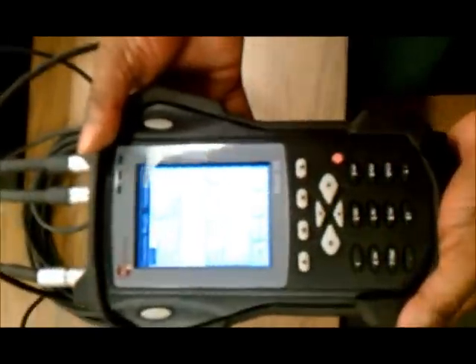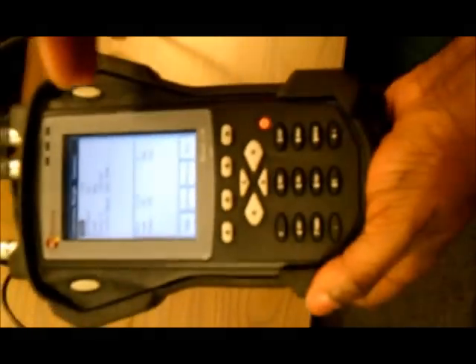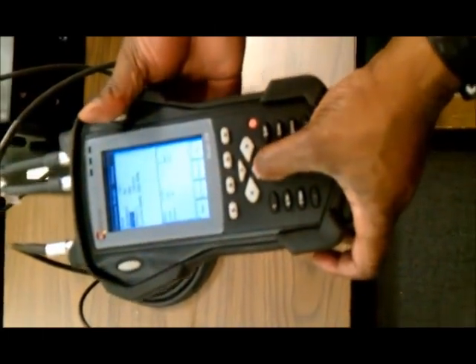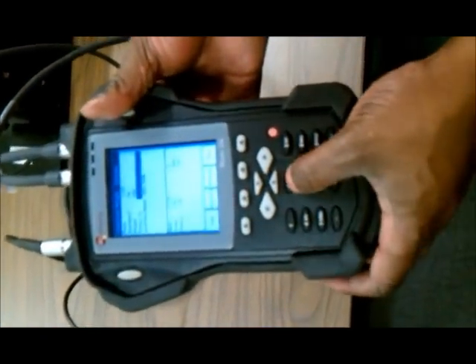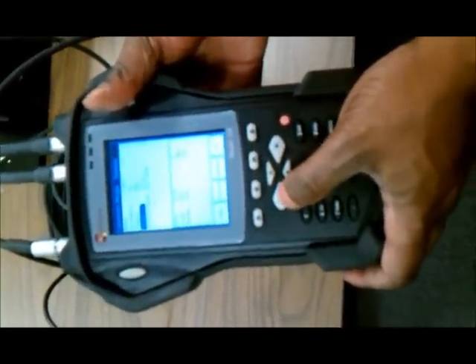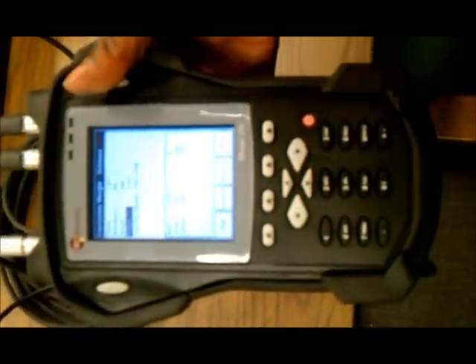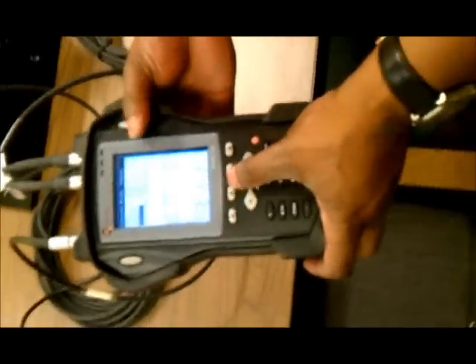And now we have our summary of what we need to do to correct it. In this instance, we need to add 0.278 grams at an angle of 144 degrees, and a radius of 1 inch. The good thing about the 258 is if we decide that 1 inch isn't where we want to add it, we can change the radius, we'll say 2 inches in this case. And what it does is it compensates. As you can see, it dropped our mass by half because we've doubled our radius. And vice versa, if we make our radius smaller, it's going to take more mass to do that.